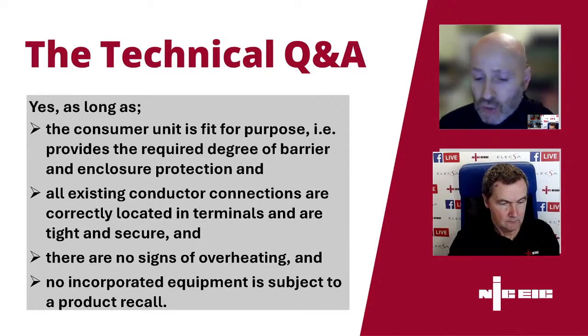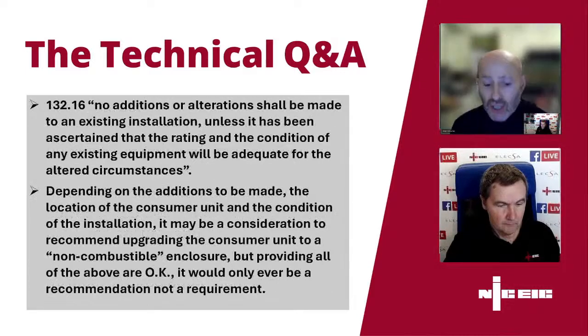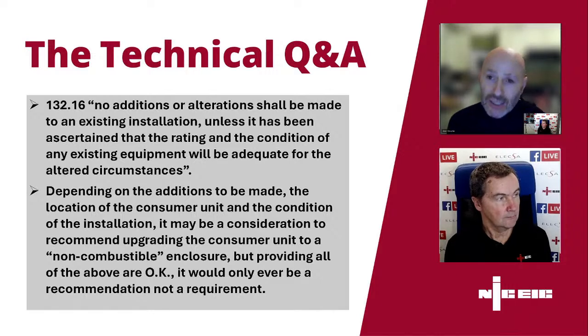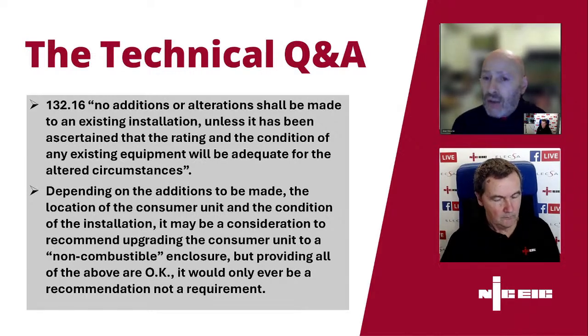No incorporated equipment is subject to a product recall. So go on to the manufacturer's websites and other websites that I've got an affiliation with, and just check that particular make and model has no recalls in place. And then what you've got to consider once you've looked at them is an actual requirement itself coming from BS 7671, which is 132.16, and it quite simply states, no additions or alterations shall be made to an existing installation unless it has been ascertained that the rating and the condition of any existing equipment will be adequate for the altered circumstances. So you must do your checks beforehand, your earthing and bonding and anything else that's relevant to that particular scope of work.